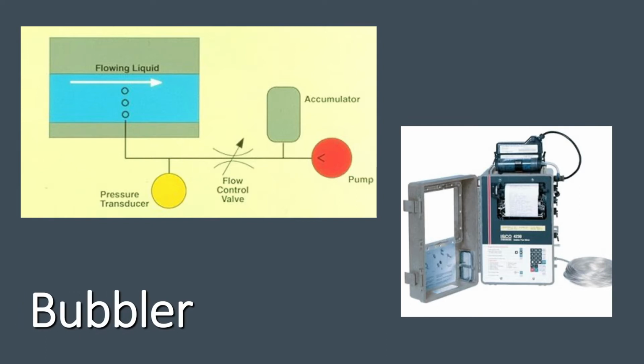Another tried and true method is the bubbler technology. Bubbler technology simply utilizes differential pressure. The flow meter has an integral compressor storage chamber, and it discharges a pressure in the form of a bubble to the flow stream, to a primary device. And the frequency of that bubble is about 1 to 2 bubbles per second. And by seeing that pressure, that the pressure transducer back in the flow measurement device sees, again, we can figure out the level of the water. Bubbler technology has been used for decades. I find it to be very repeatable.